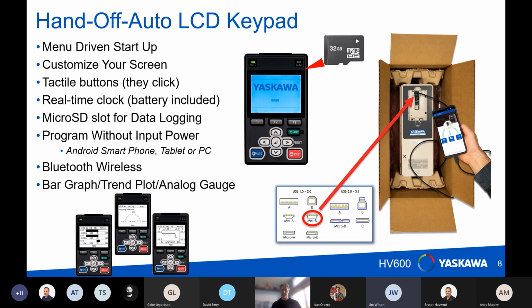So that can be a pretty powerful tool. And the 32, we now added the keypad. You can put a micro SD card in to automatically, continuously trend certain parameters. The way we used to have to do it is if you had a problem and we needed to trend those monitors, we'd have to leave a laptop in the panel overnight and then go back. And it was kind of the luck of the draw if the problem occurred again.